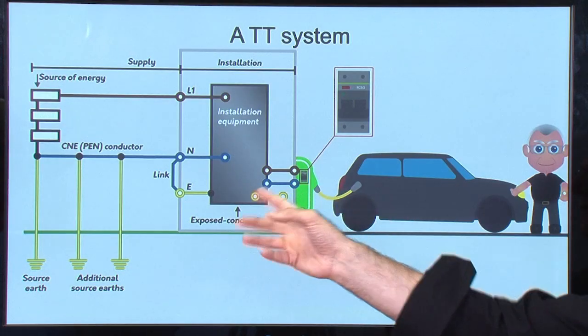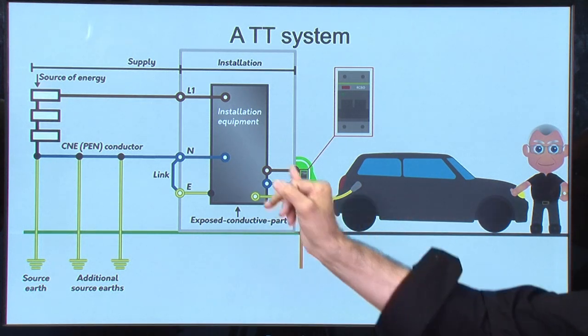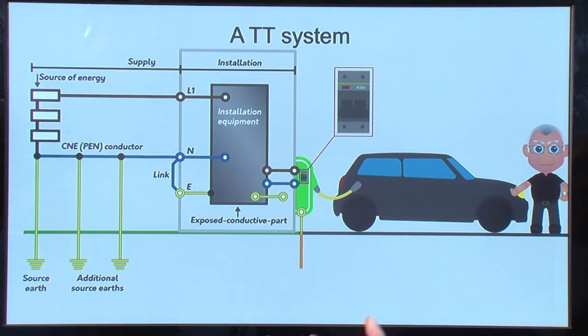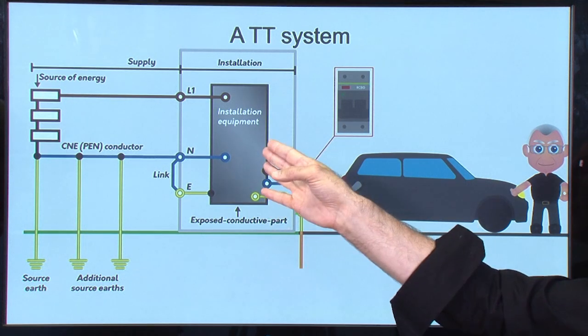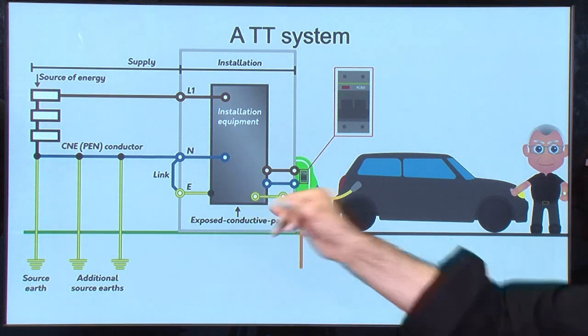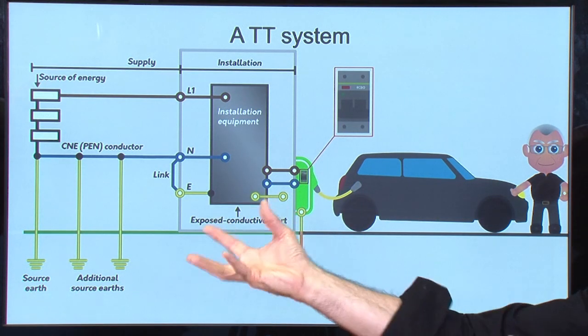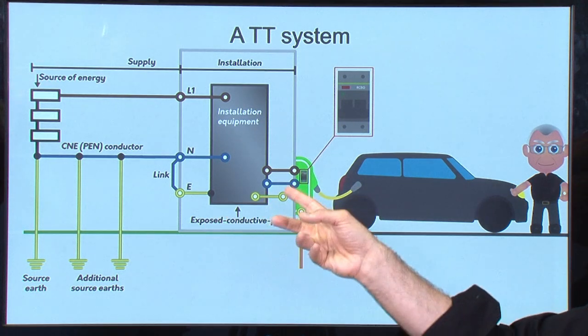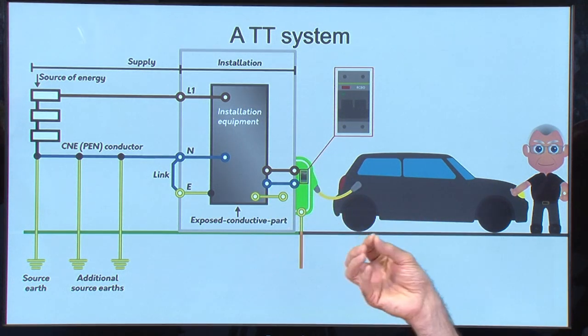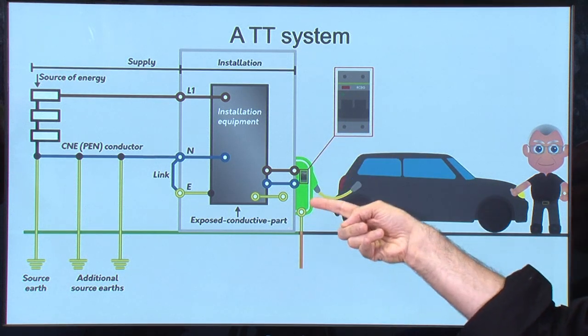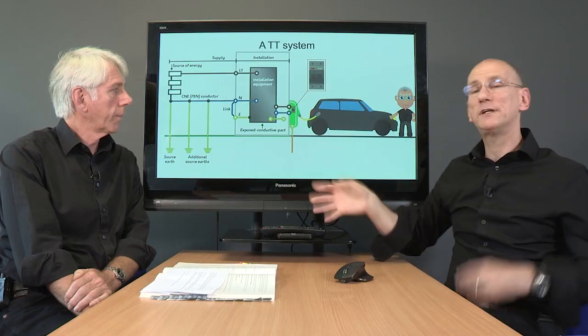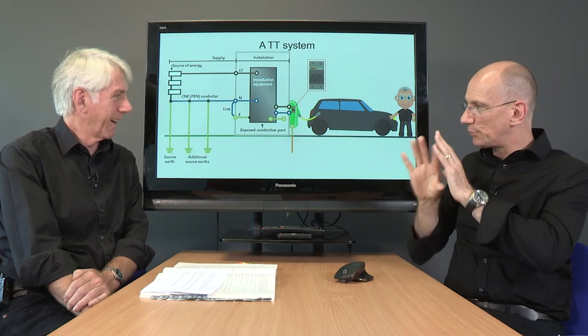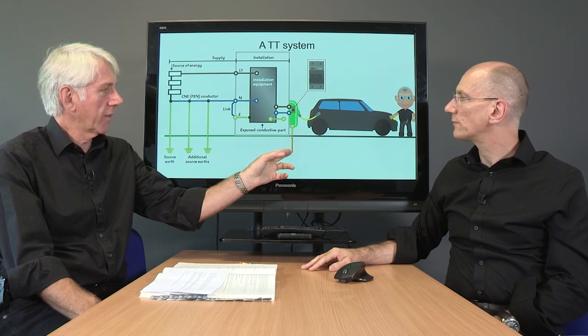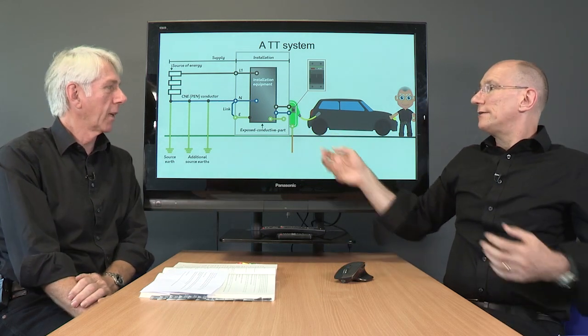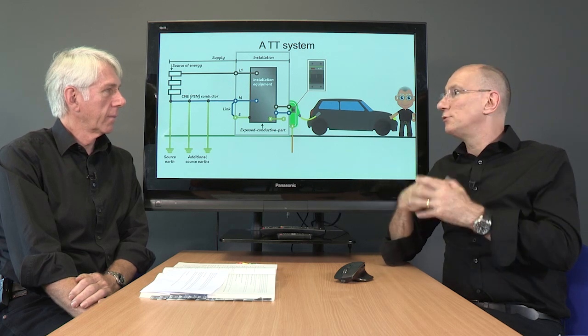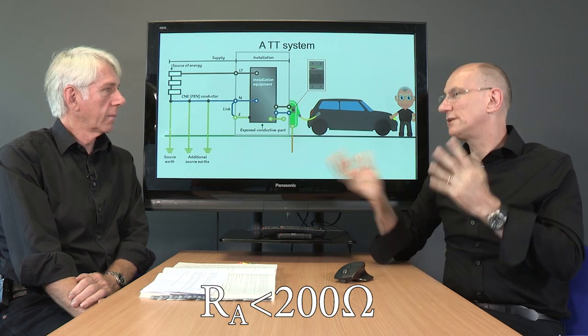Yeah. Okay. So, it's a little bit difficult to see the lengths of cables here, but this particular cable could be an SWA cable as an example. And basically what we would do is have all the overcurrent protection at the origin, and the armouring would be earthed up on the installation. Yep. But when you come to the EV charging point, the earthing arrangement would be via an earth electrode, which is nothing to do with tying into the main earth. This is completely separate. And so the onerous task of getting that resistance down would not apply. Wouldn't apply. Yeah. Because you've made a TT arrangement, we are looking at normal arrangements, so typically less than 200 because it can become unstable.